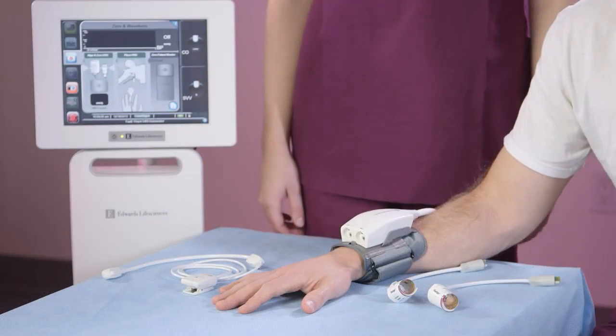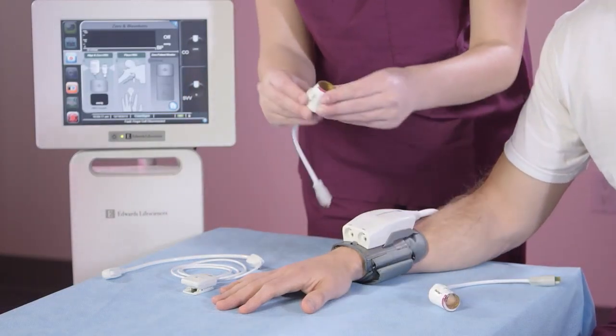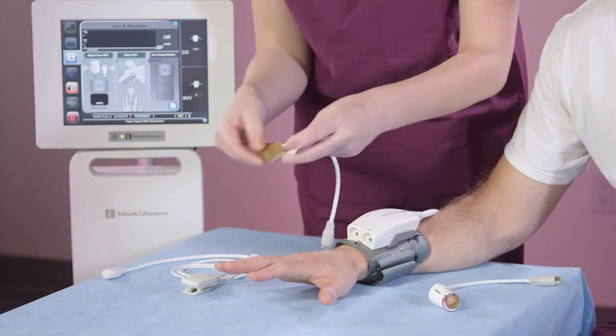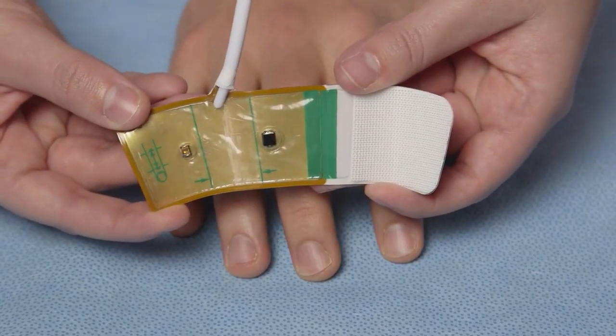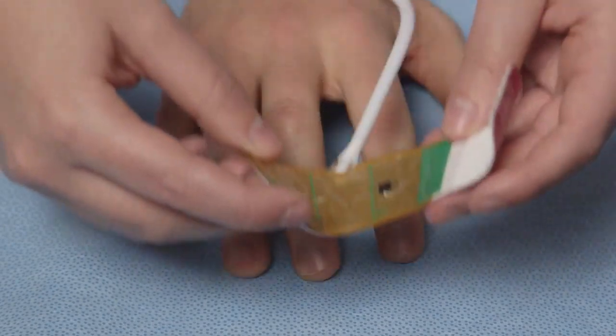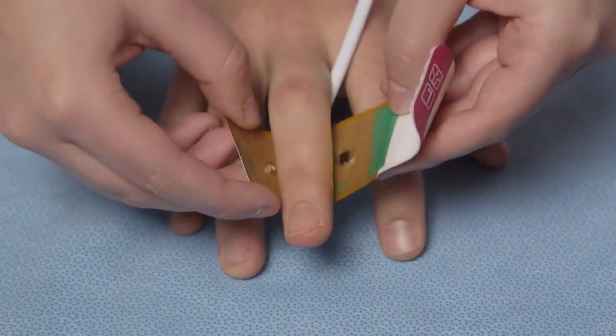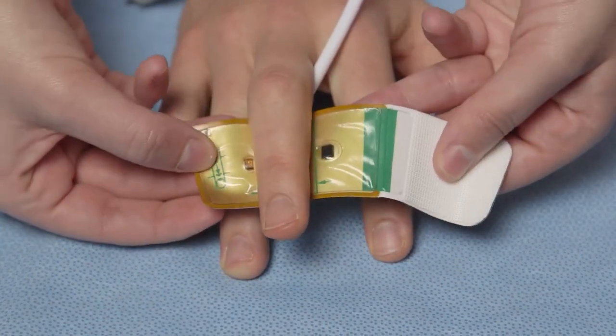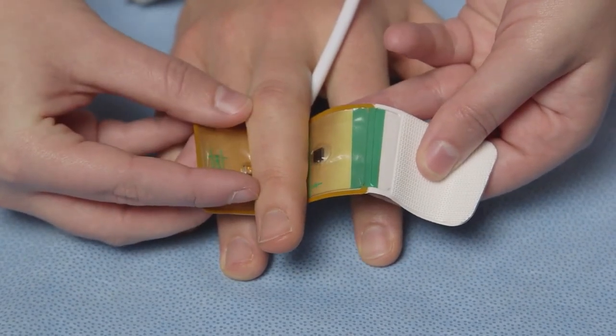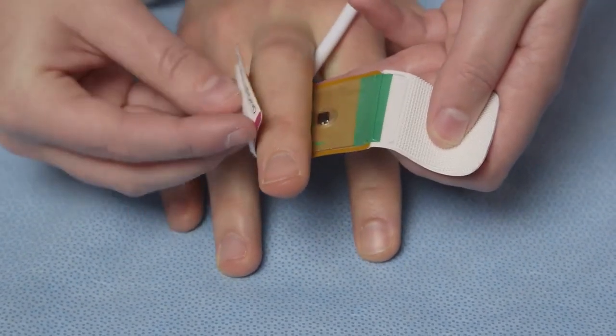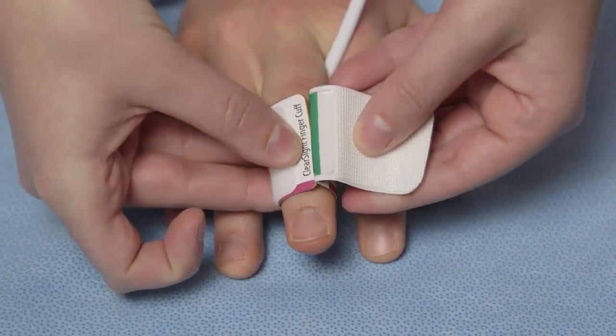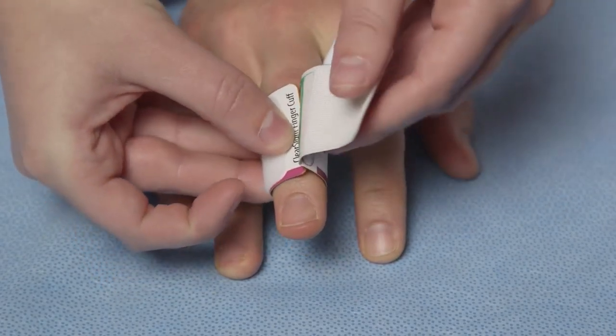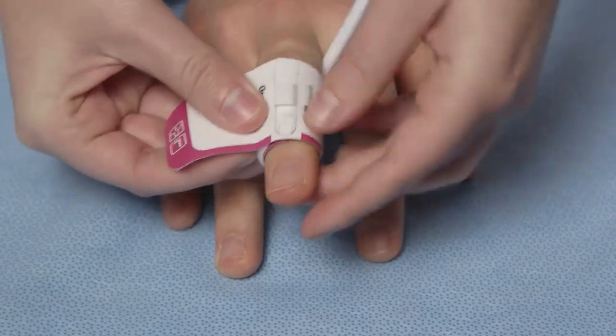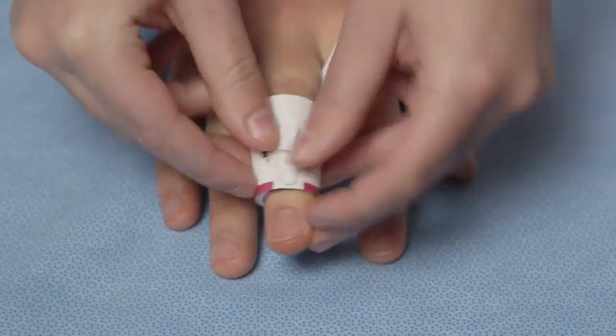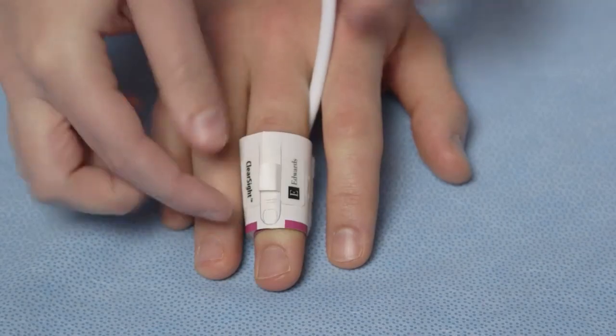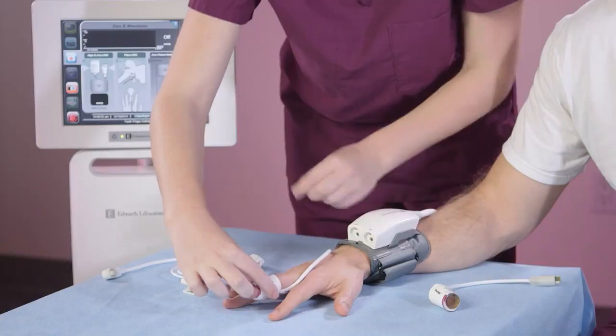Proper placement of the finger cuff is critical to assure accurate readings. To apply the finger cuff, approach the finger from underneath, placing the index, middle, or ring finger in cuff number 1 between both optical components and center the cuff between the two knuckles. Wrap the finger cuff snugly around the contour of the finger, ensuring that the end of the finger cuff lies inside the green zone. The air hose should be positioned underneath the patient's finger. The finger cuff is sufficiently tight when a gentle tug on the cuff does not remove it from the finger.